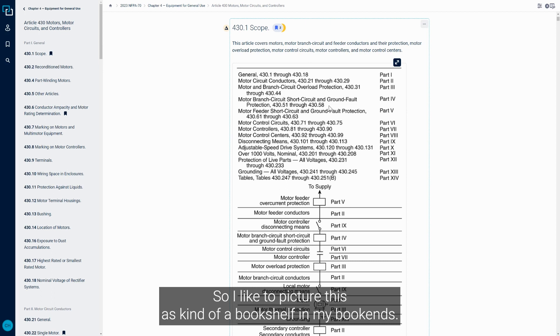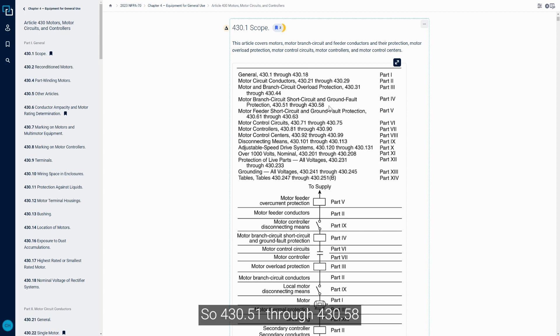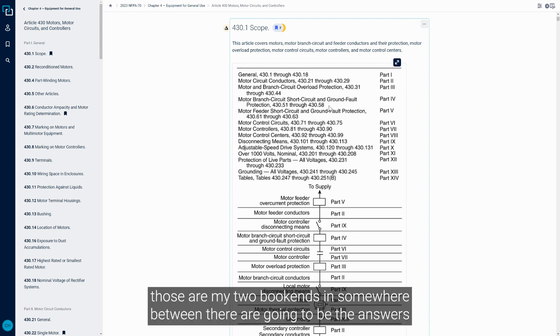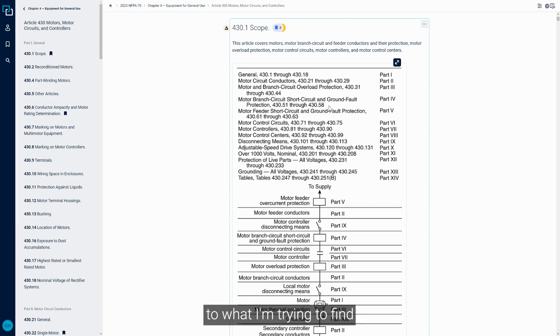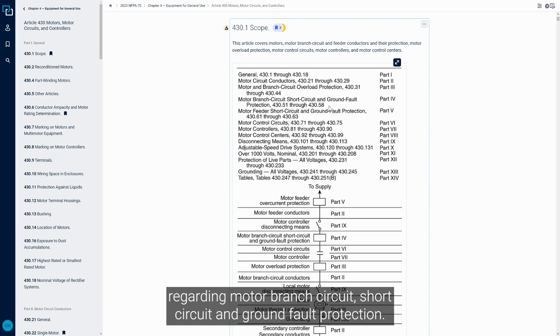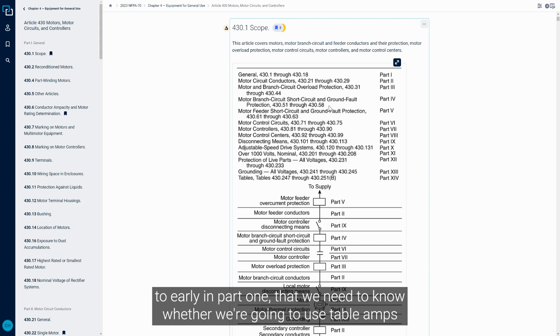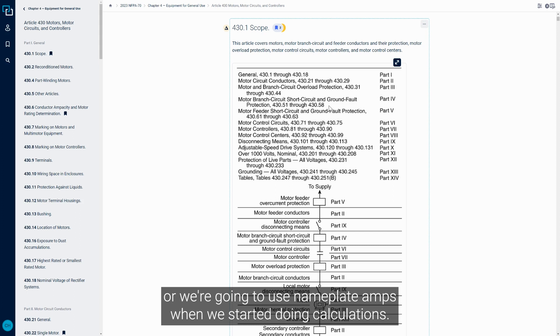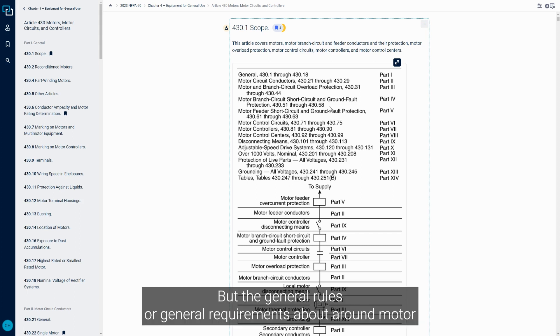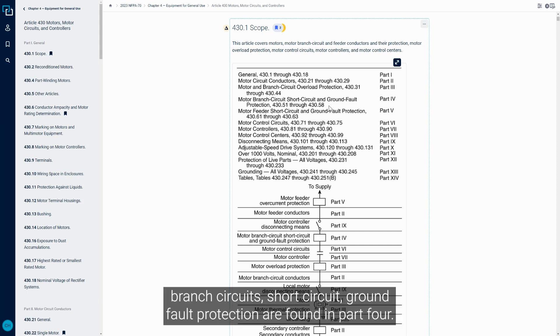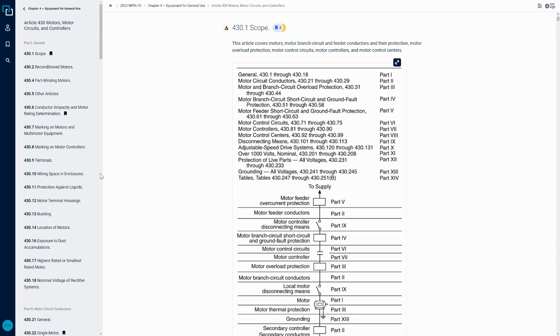I like to picture this as kind of a bookshelf with my bookends. So 430.51 through 430.58, those are my two bookends. Somewhere between there are going to be the answers to what I'm trying to find regarding motor branch circuit short circuit and ground fault protection. There's a few other caveats - early in Part 1 we need to know whether we're going to use table amps or nameplate amps when we start doing calculations.